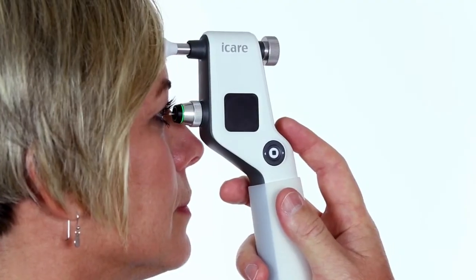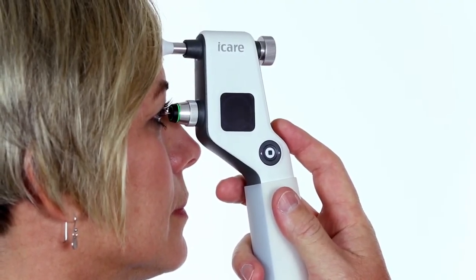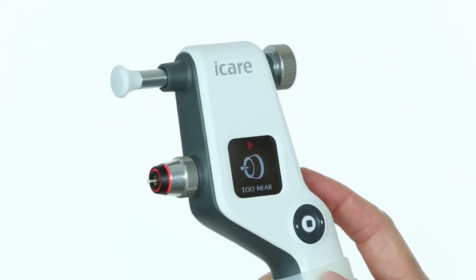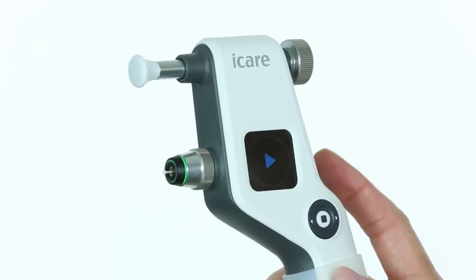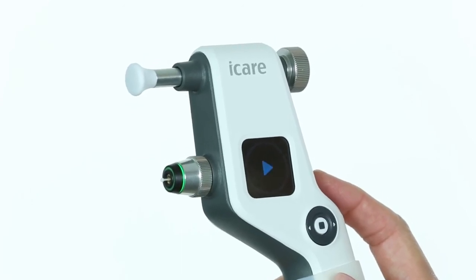Error Messages. For example, if you are too close to the cornea, the too near error message will display and the probe base light flashes red. Clear the error message by pressing the measure button once.